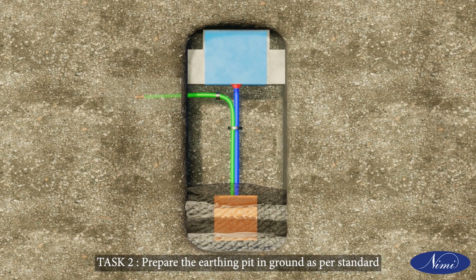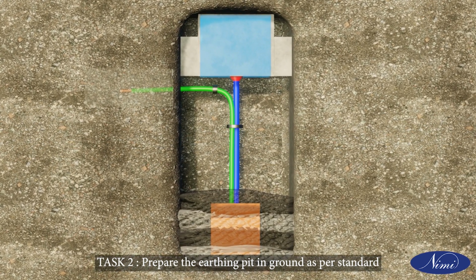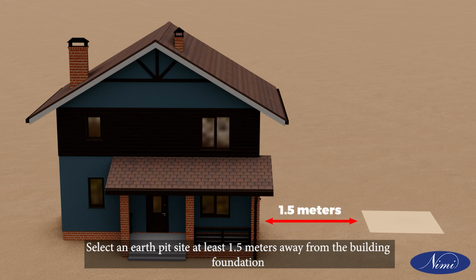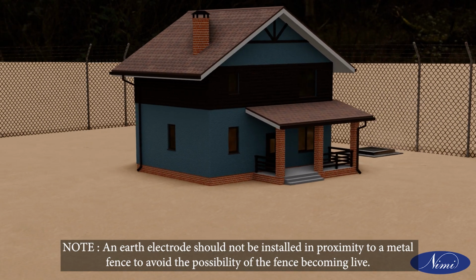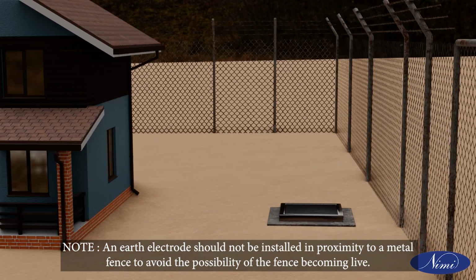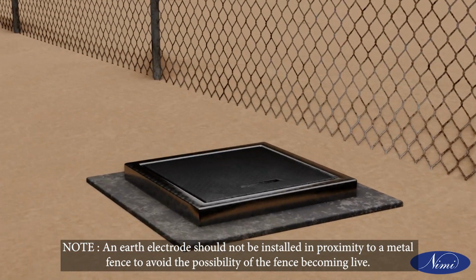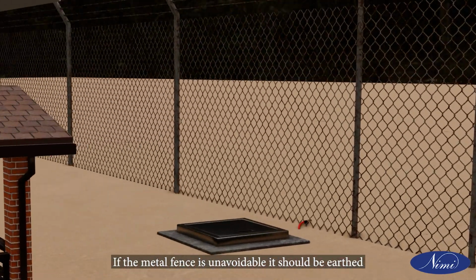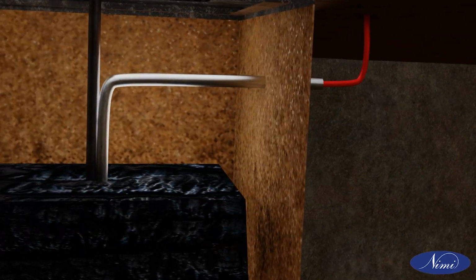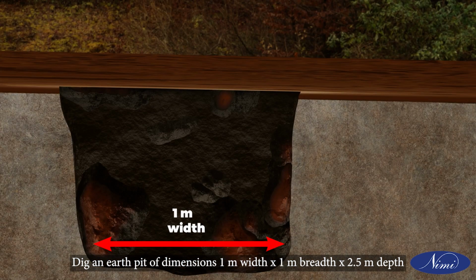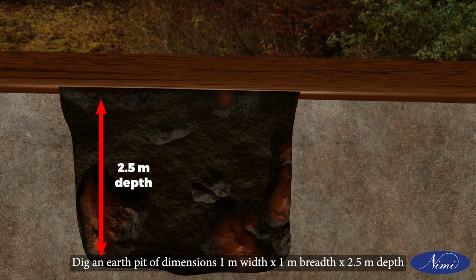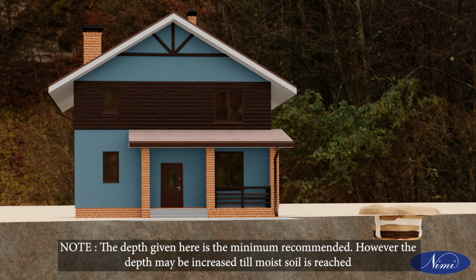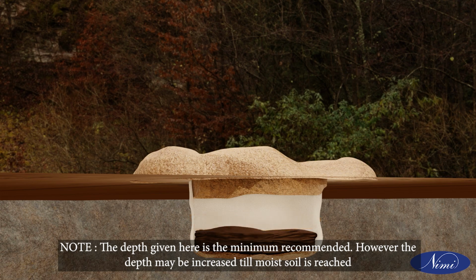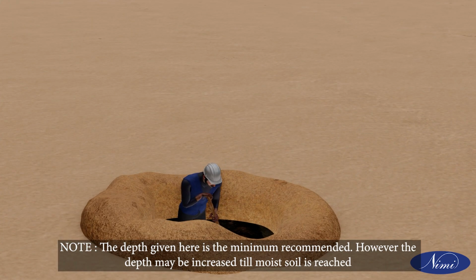Task 2. Prepare the earthing pit in ground as per standard. Select an earth pit site at least 1.5 meters away from the building foundation. Note: an earth electrode should not be installed in proximity to a metal fence, to avoid the possibility of the fence becoming live. If the metal fence is unavoidable, it should be earthed. Dig an earth pit of dimensions 1 meter width into 1 meter breadth into 2.5 meter depth. Note: the depth given here is the minimum recommended. However, the depth may be increased till moist soil is reached.